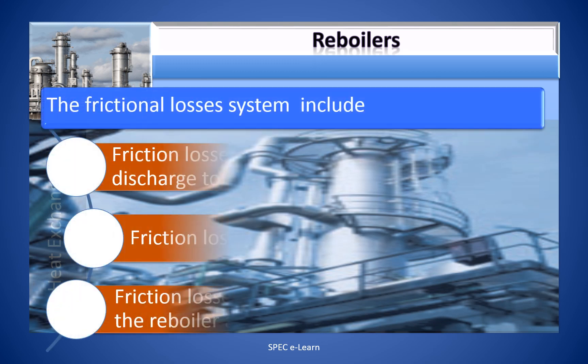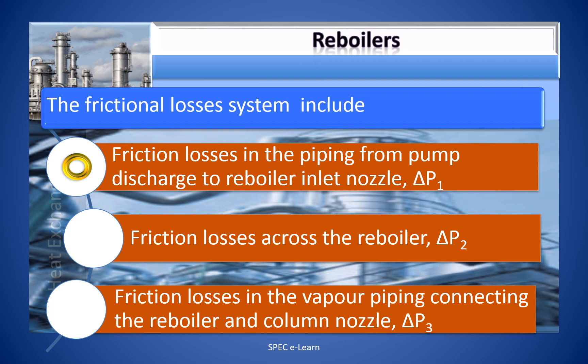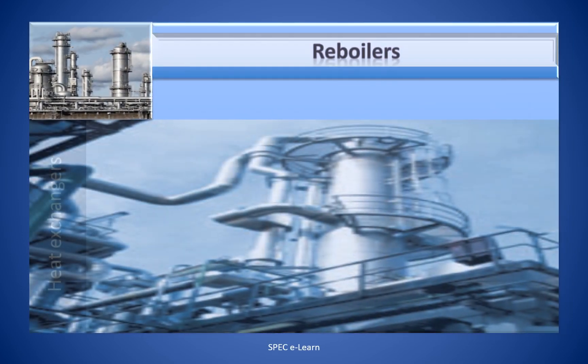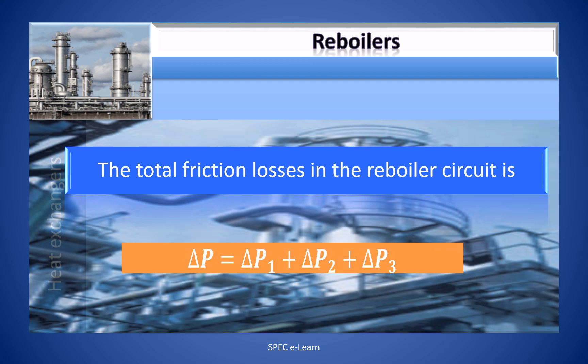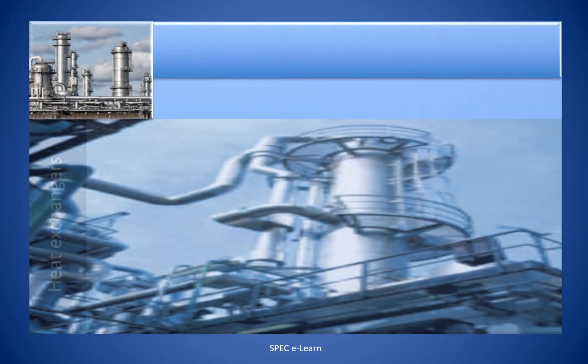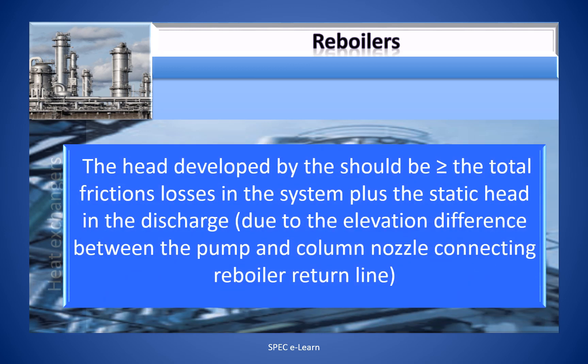The friction losses in the system include: friction losses in the piping from the pump discharge to the reboiler inlet nozzle (ΔP1), friction losses across the reboiler (ΔP2), and friction losses in the vapor piping connecting the reboiler and the column nozzle (ΔP3). The total friction losses in the reboiler circuit is ΔP = ΔP1 + ΔP2 + ΔP3. The head developed by the pump should be greater than or equal to the total friction losses plus the static head due to the elevation difference between the pump and the column nozzle connecting the reboiler return line.